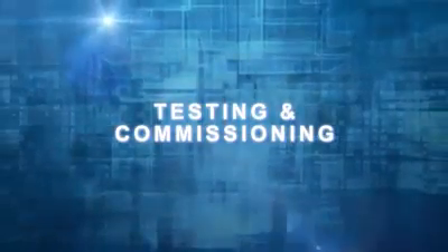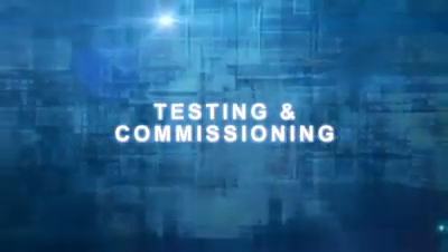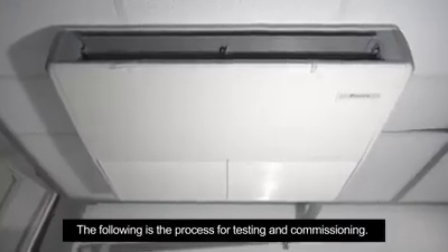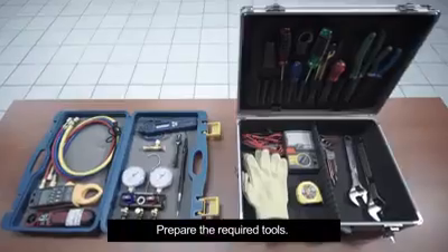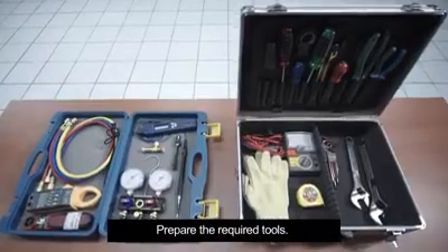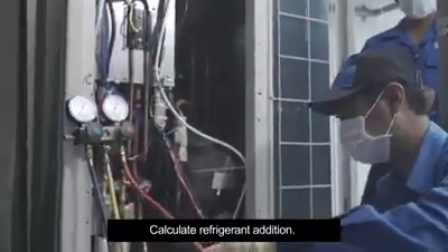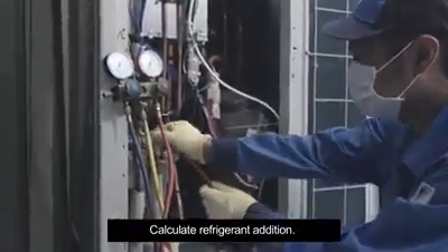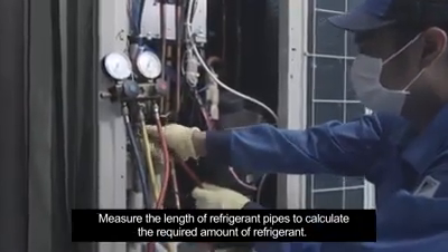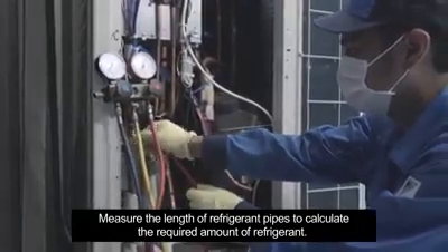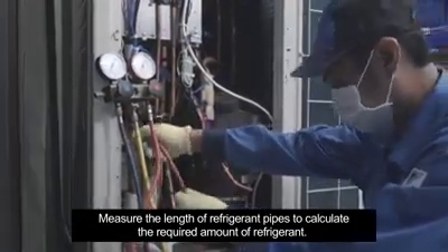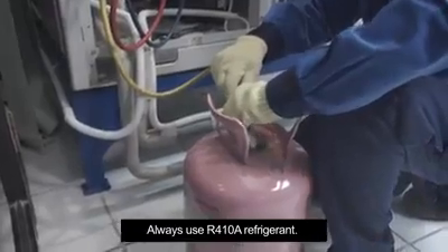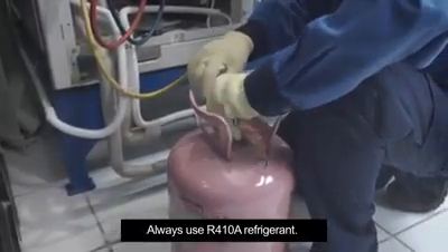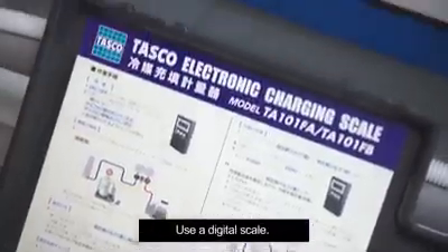Testing and commissioning. The following is the process for testing and commissioning. Prepare the required tools. Calculate refrigerant addition. Measure the length of refrigerant pipes to calculate the required amount of refrigerant. Always use R410A refrigerant. Use a digital scale.